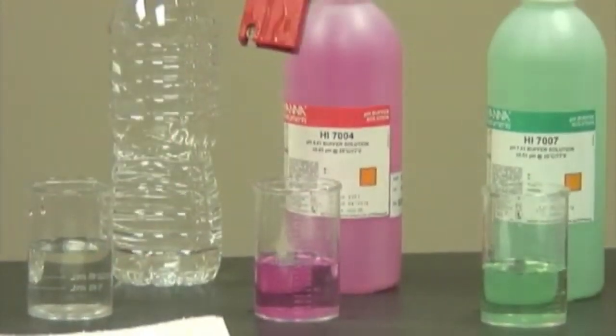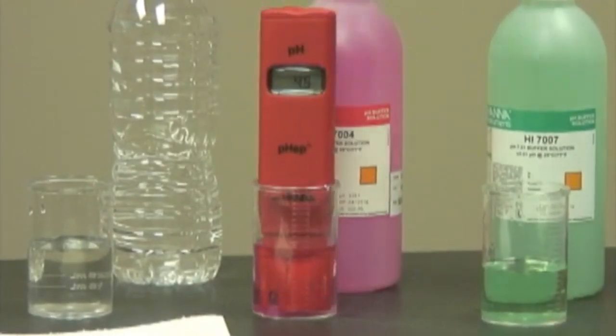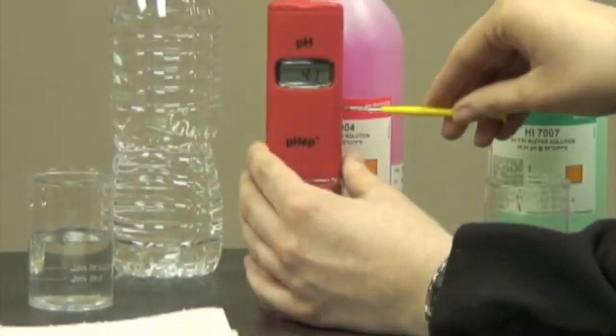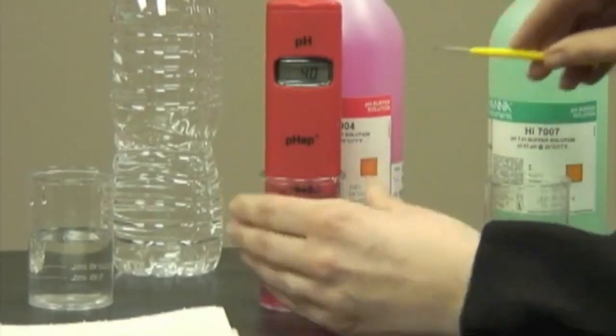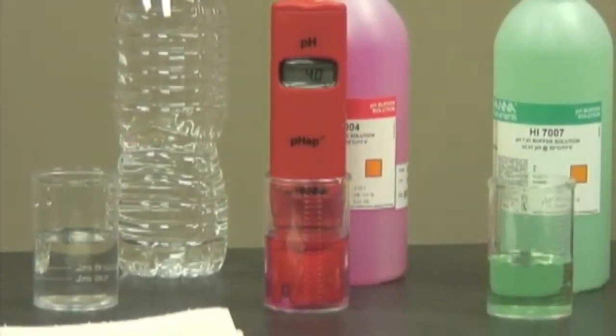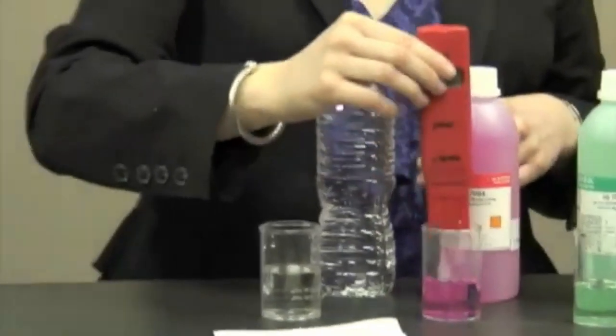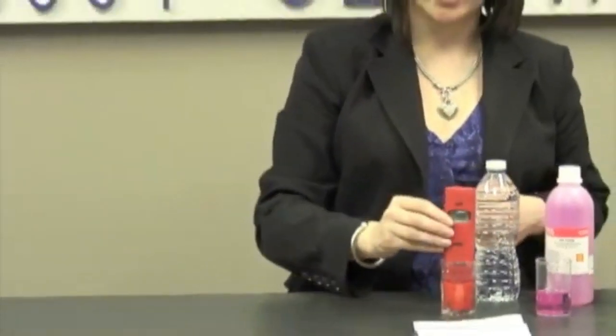and because I'm measuring an acidic solution, I'm going to do it in a pH 4 buffer. And then I'm going to take the instrument and calibrate it until it reaches pH 4. Now I'm ready to do my measurement. So I'm going to rinse it off one more time, and then I'm going to perform my test.